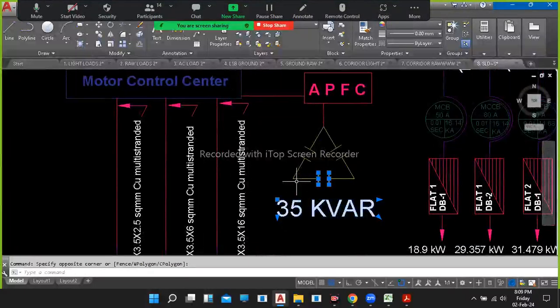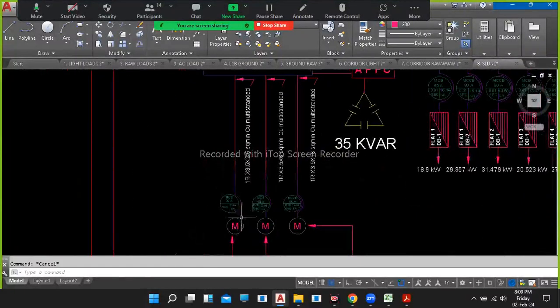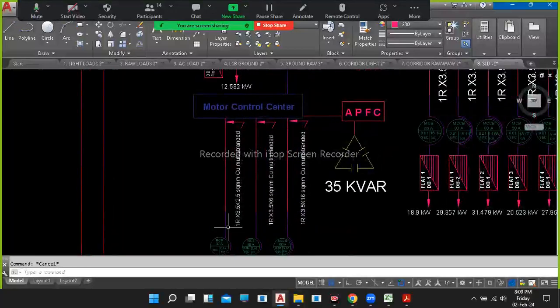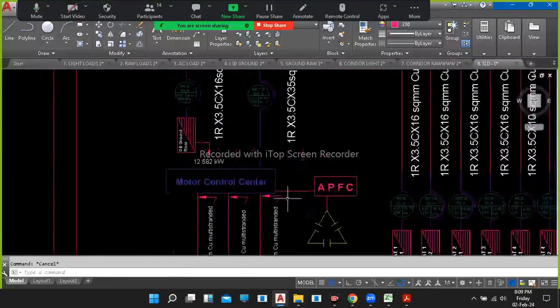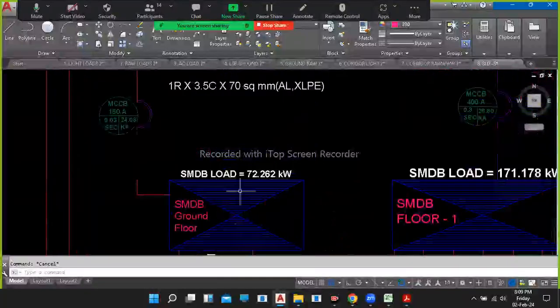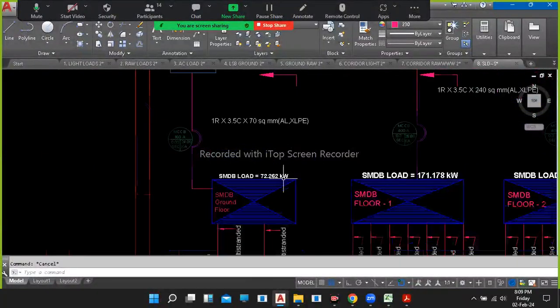See. So never put a common capacitor. Here you should never put a common capacitor. Individual capacitor for individual motor, because there is individual compensation. So this motor separate, this motor separate, this motor separate capacitor. Then adding up this and this, we got the SMDB ground floor load 72.262 kilowatt. Adding up all this, you got the MDB load.